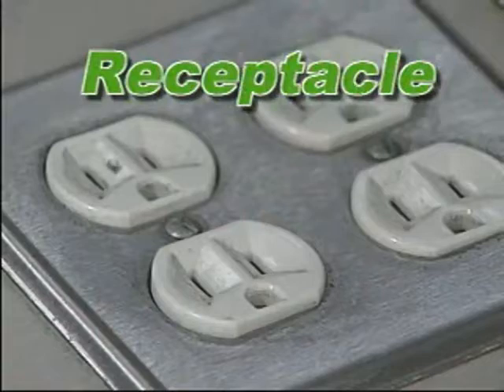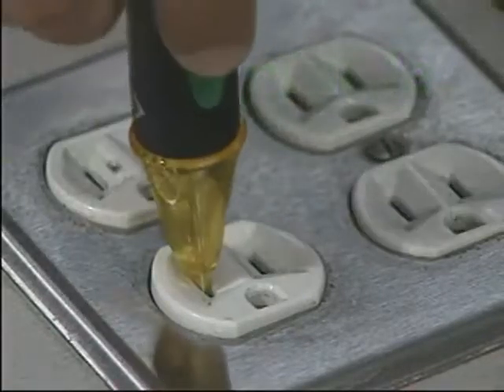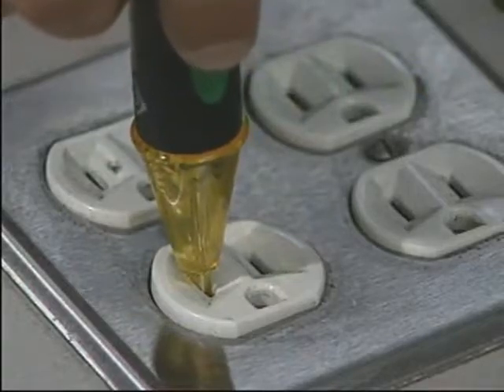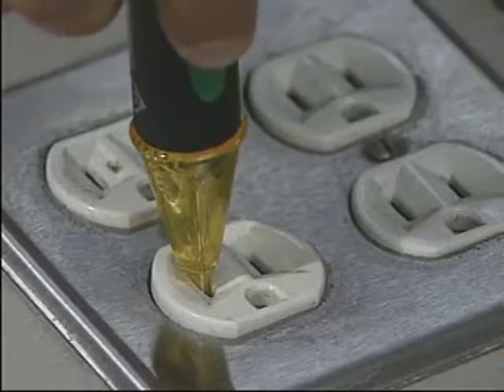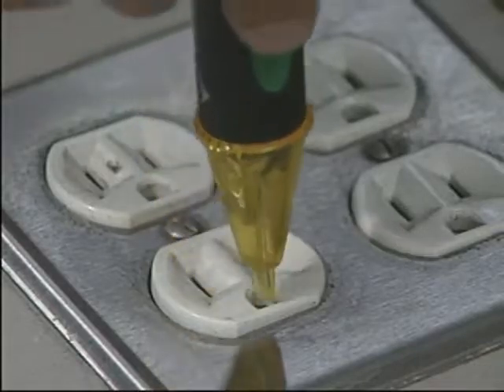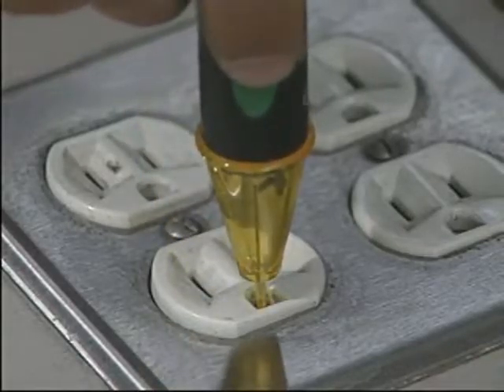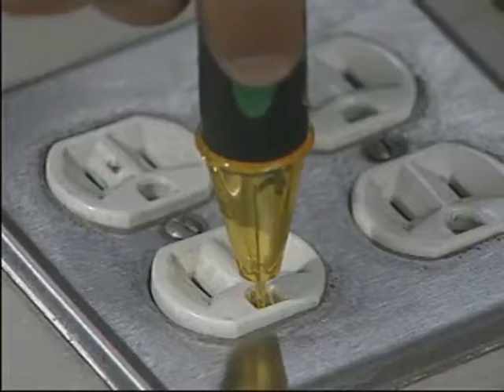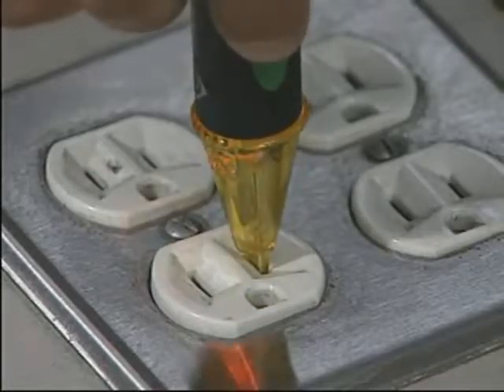To test a receptacle, insert the probe tip into the large slot. There should be no audible or visual alarm. If there is an alarm indication, the receptacle has been improperly wired. Insert the probe tip into the U-ground. There should be no alarm indication. Insert the probe tip into the small slot. There should be an audible and visual alarm.